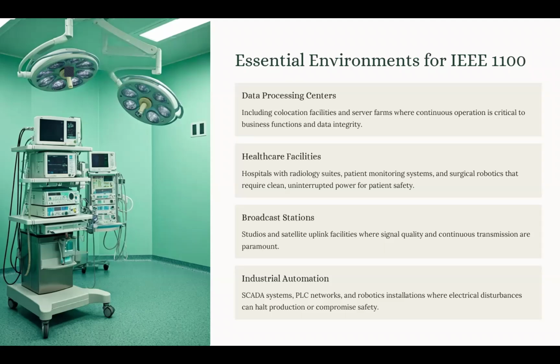Now, there is another essential kind of sensitive environment, which is the healthcare facility. We know that medical equipment like MRI or CT scanners, surgical robots, and patient monitors are life critical. So even momentary power anomalies can cause diagnostic error or surgical interruption and very harsh consequences. Now, some of the IEEE practices that are recommended for this kind of environment are functional grounding for medical electronics and strict voltage and transient control.